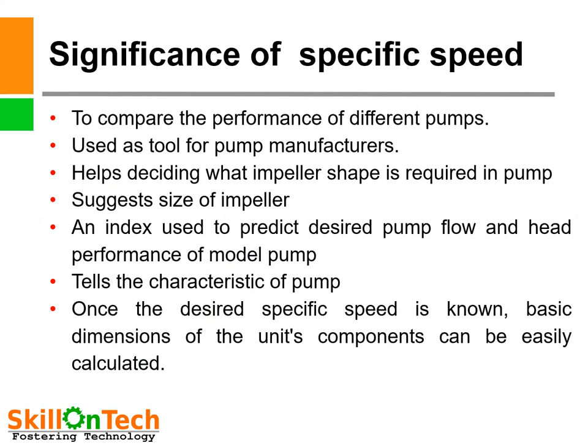What is the significance of specific speed? It is used to compare the performance of different pumps, and serves as a tool for pump manufacturers. It helps decide what impeller shape is required, suggests the size of the impeller, and is an index used to predict desired pump flow and head performance of a model pump. It tells the characteristics of the pump, and once the desired specific speed is known, the basic dimensions of the unit components can be easily calculated.